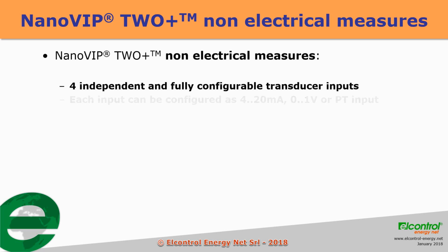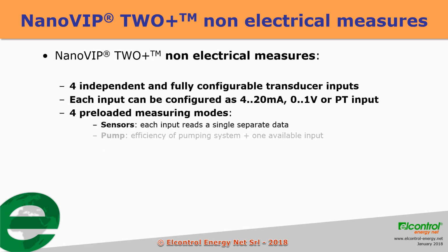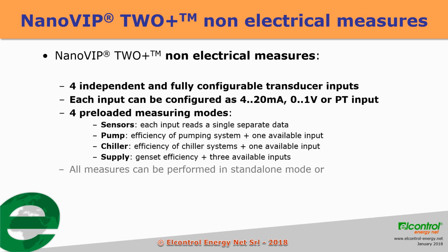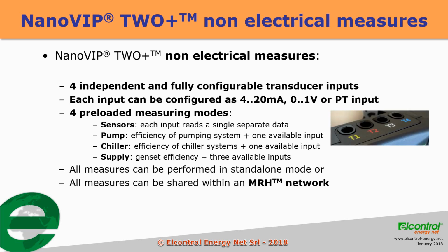NanoVIP 2 Plus adds thermomechanical measures to standard electrical measures. 4 independent and fully configurable transducer inputs. Each input can be configured as 4-20 mA, 0-1 volts or PT100 input. 4 preloaded measuring modes. Sensors: each input reads a single separate data. Pump: efficiency of the pumping system plus 1 available input. Chiller: efficiency of chiller systems plus 1 available input. Supply: Genset efficiency plus 3 available inputs. All measures can be performed in standalone mode or all measures can be shared within an MRH network.